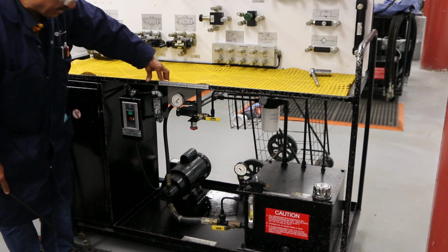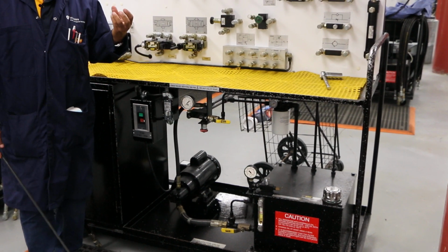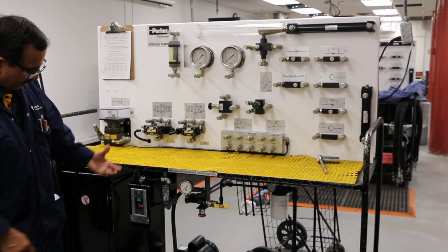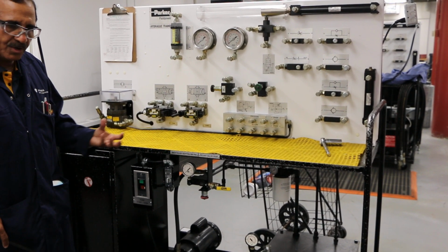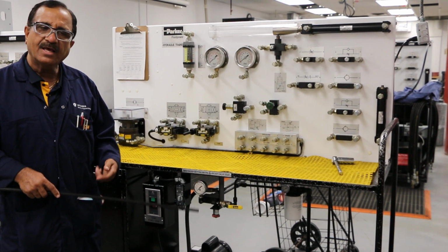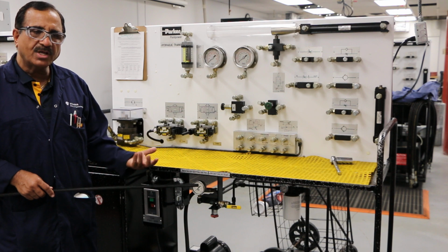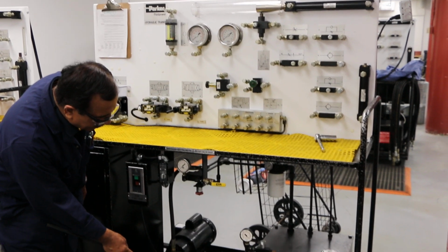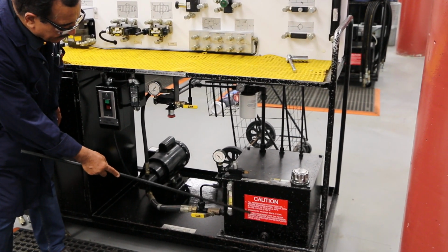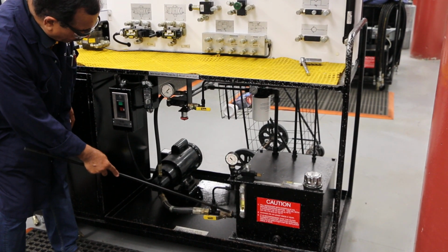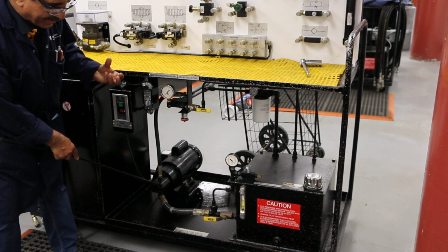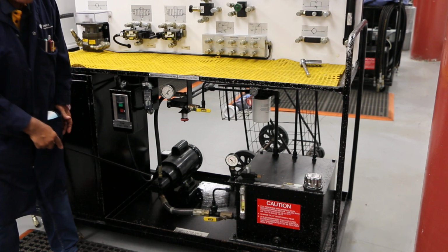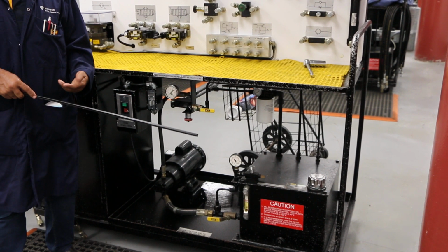Now what is cavitation? It's when the pump starves of oil and cavitation is created. Cavitation means that there is not enough oil going to the pump, and the components inside the pump run metal to metal and the pump burns in a few seconds. Now how does that happen? It is mainly when the suction strainer inside the tank, a little suction filter here that picks up all the impurities before the oil goes to the pump so that the pump can have a longer life, gets dirty. When the suction strainer is dirty, you don't have enough oil going to the pump, and the pump components run metal to metal and the pump burns.